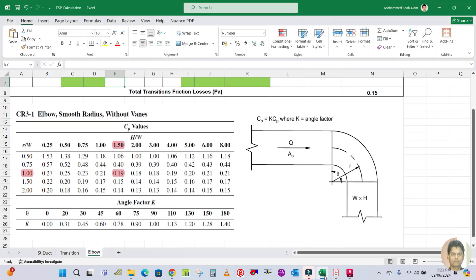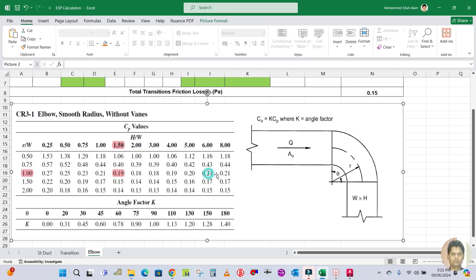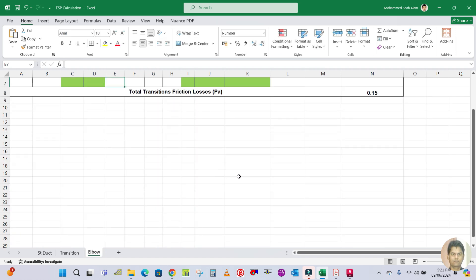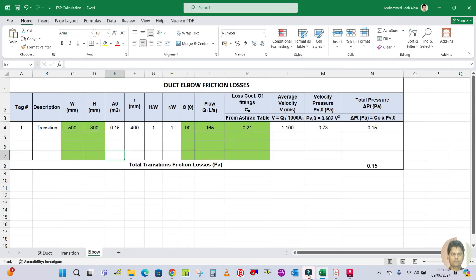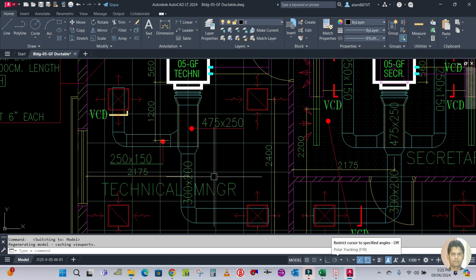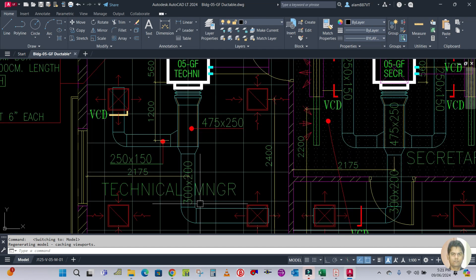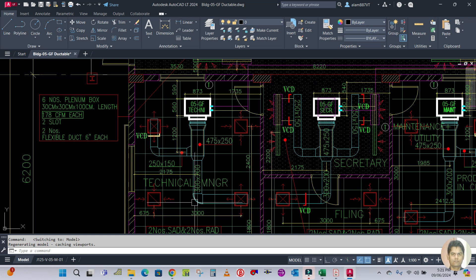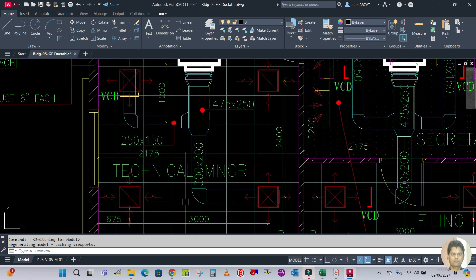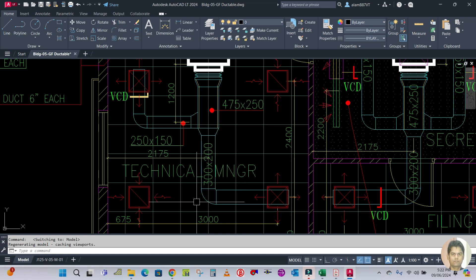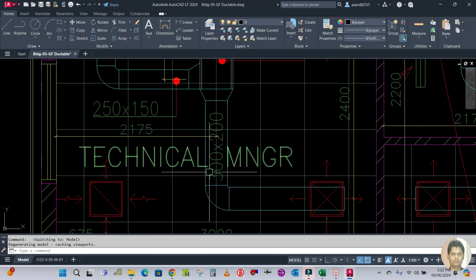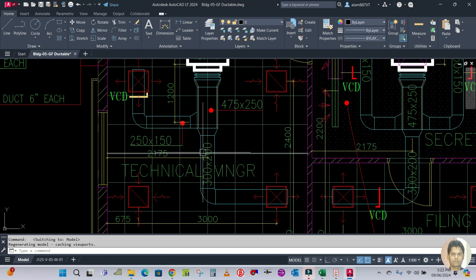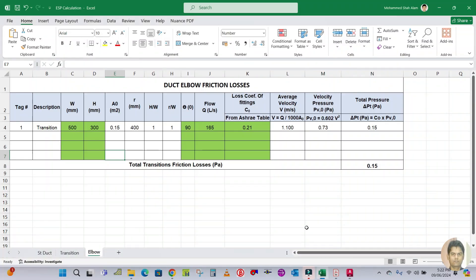Let us start now. I have taken a screenshot from the handbook. This is the elbow and this is the critical path where we want to calculate the pressure drop. In this path only one elbow is present. The size of the elbow equals the duct size — the duct size is 300 by 200, so elbow width and height are also the same.